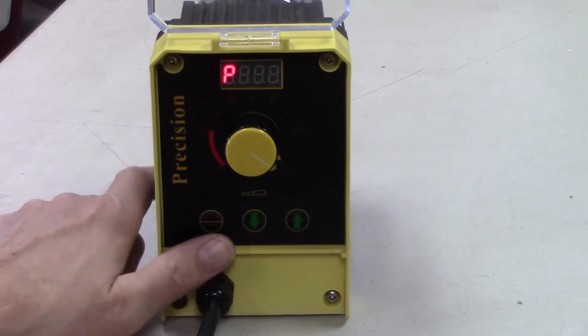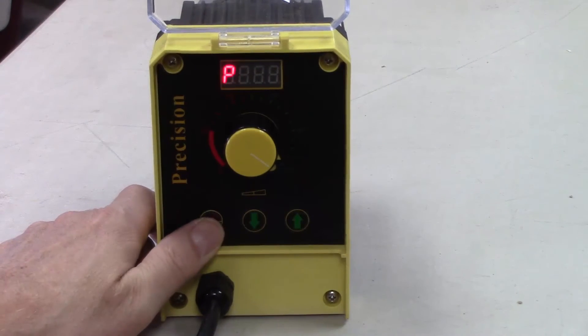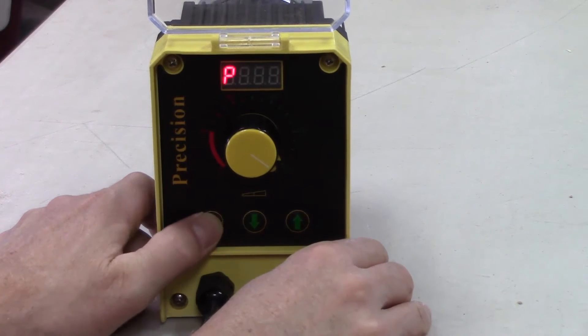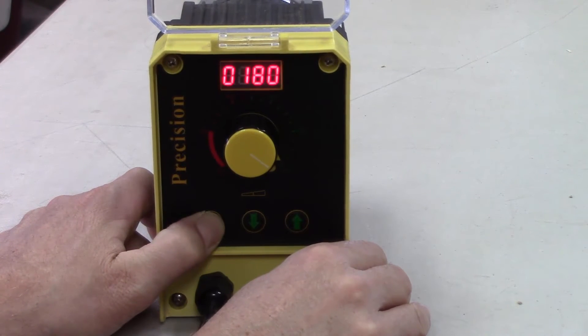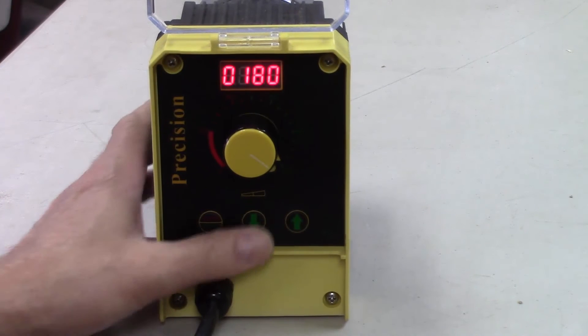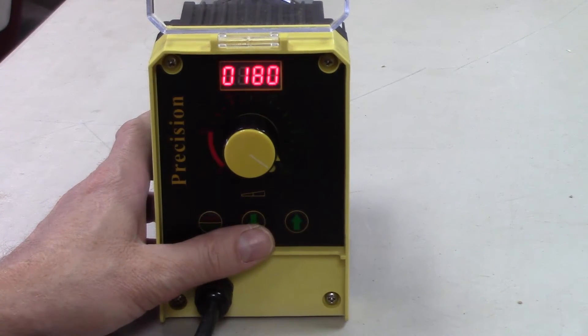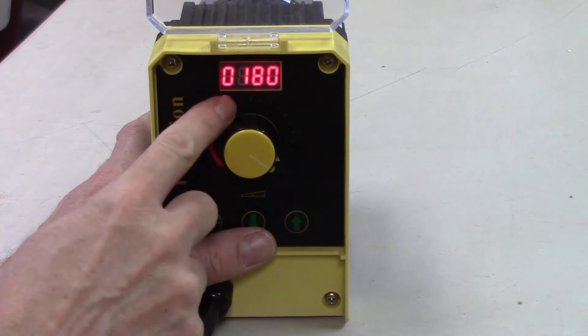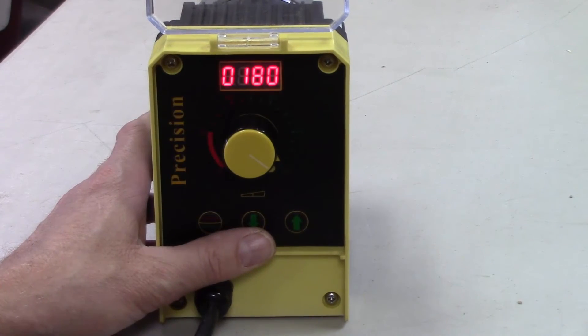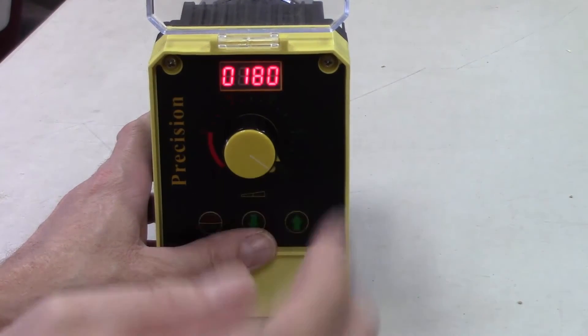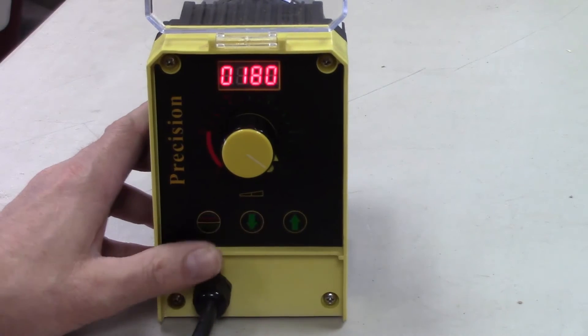If you press and hold the start/stop button while it's on P, then after a few seconds you'll go into the very brief programming menu. All you really ever need to know is that zero has to be at 180. That's so that the pump will pump the maximum number of times, which is three times a second.